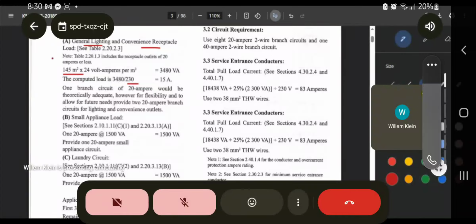Okay, so for this one you'll already have 2 branch circuits, and then your small appliance loads. Usually it's 1500 VA. So that covers your small appliance load. This can be a combination of a small TV, let's say a small oven, something like that. And this is already according to standard. So you can provide one 20 ampere small appliance circuit. So it means another 20 ampere branch circuit.